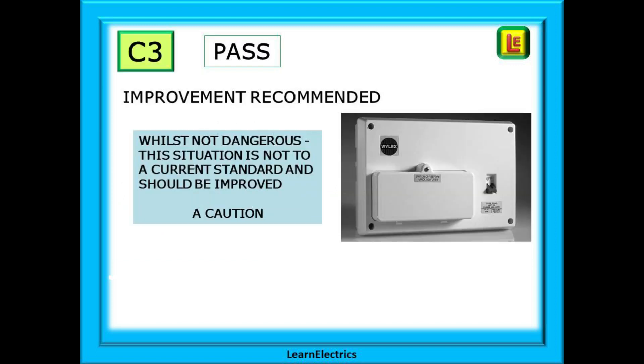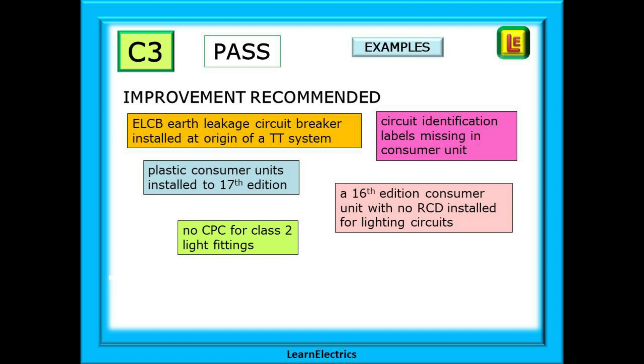A C3 is improvement recommended. Whilst not dangerous, this situation is not to a current standard and should be improved. Quite often this occurs when an older installation was installed to a previous edition of the regulations and still conforms to that older version, but does not comply with the latest additions or amendments. It's a caution really — there are opportunities for improvement. Here are a few examples of C3 codes to consider.